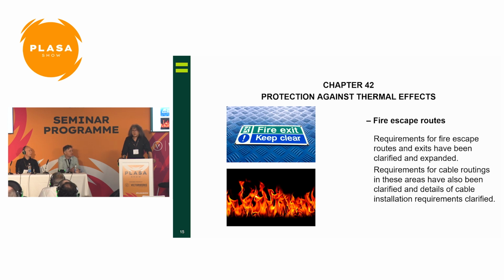Part 5 of BS 7671 talks about protected escape routes - these are the stark kind of staircases you see in football stadiums, for example. It's a concrete staircase, there's a handrail, there might be treads on the edge of the steps, there might be a light and fire alarm system, but that's it, nothing else going on in there. Places like that, the owner of the building will not give permission to run cables through. If that's the only route, you need to put provisions in to ensure it maintains that protected status as a protected escape route. That's another part of BS 7671, but it does feed into this as fire escape routes - so that's something to consider.